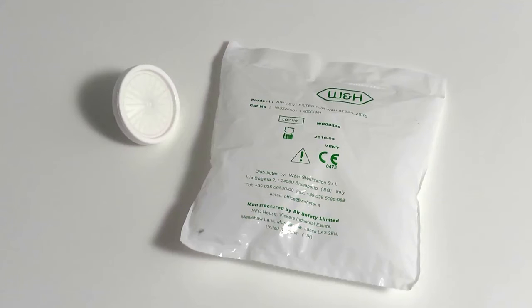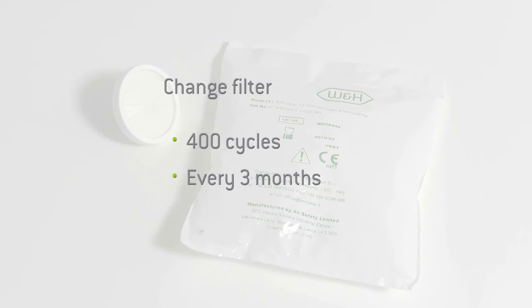The bacteriological filter should be replaced at regular intervals of 400 cycles or every 3 months, whichever is sooner. By replacing the filter, you ensure your sterilizer has a component that remains effective at filtering the air which passes through it. If the bacteriological filter is heavily discolored with dust, it should be replaced immediately.